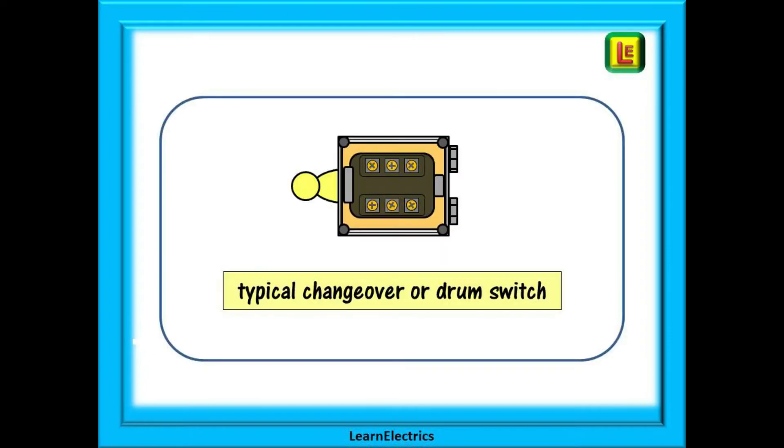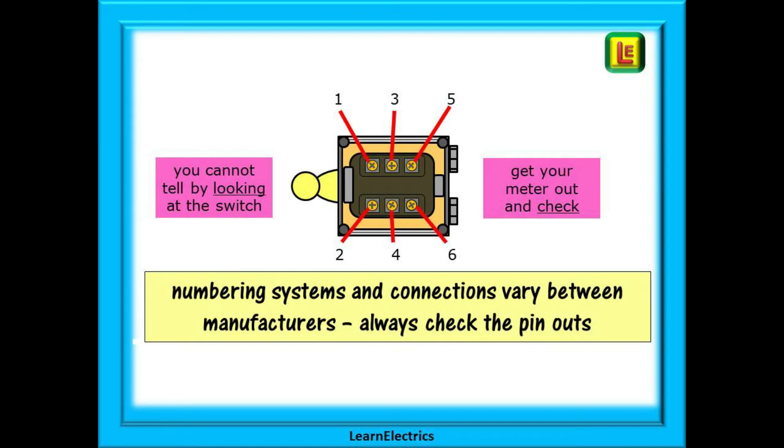This drawing is typical of a three-phase changeover switch. There are many manufacturers and they all seem to have their own preferred styles and connections. Always check the pin outs of any switch that you are unfamiliar with. You cannot tell what the internal connections and crossovers are from the outside. You'll need to get your meter out and do continuity checks if you don't have an electrical drawing for that exact switch.